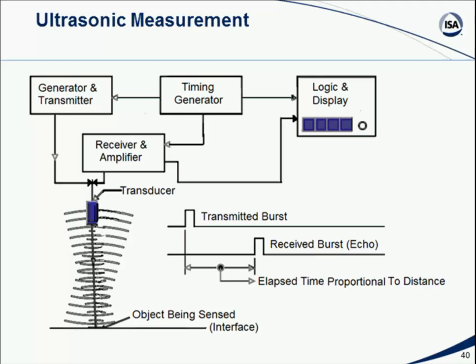We can send a sound burst downwards from the top of a tank into and through the tank, and the sound burst can hit the fluid or solid material and bounce back. If we're timing it appropriately, based on the time, we can calculate distance. Also, the speed of sound through air is proportional to the air temperature, so quite often when we use ultrasonic measurement, we may also be making a temperature measurement at the same time, so we can correct for that speed differential.